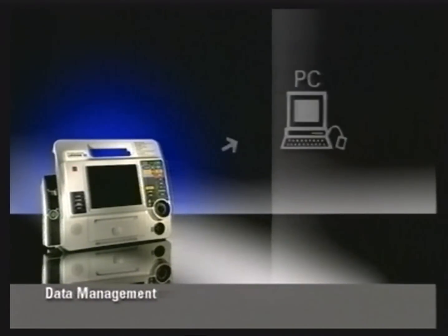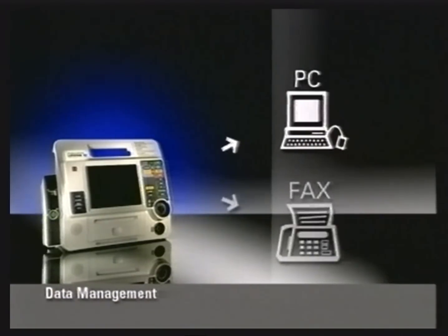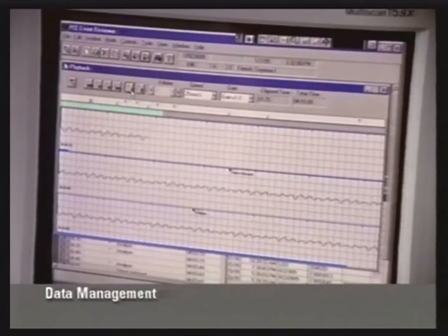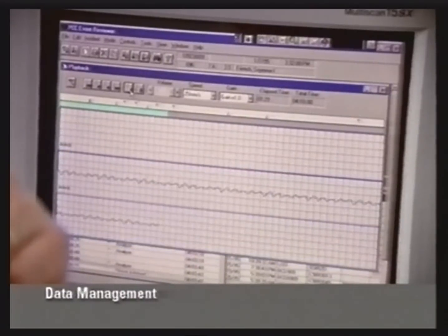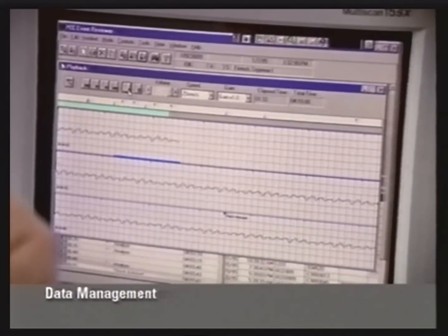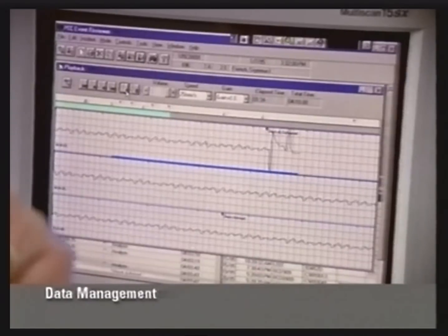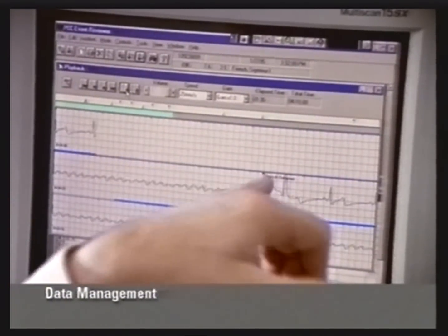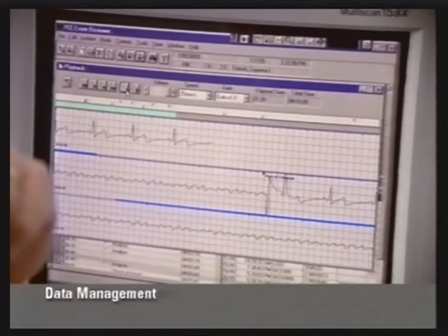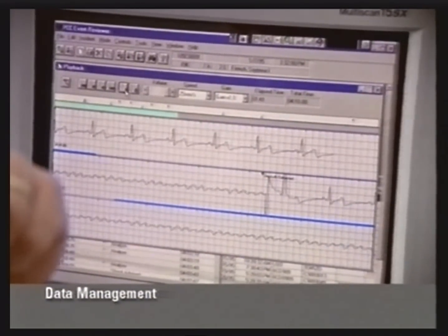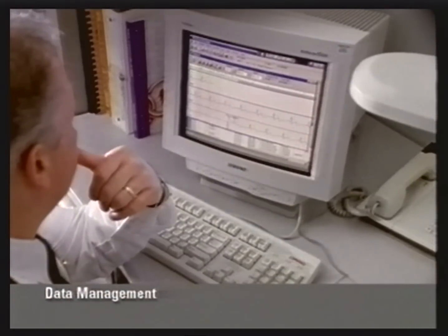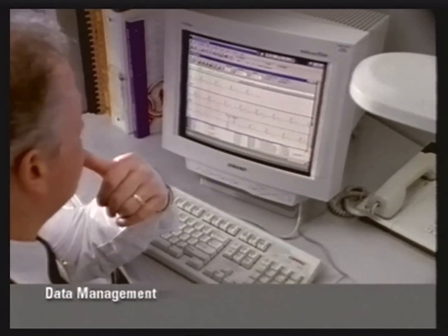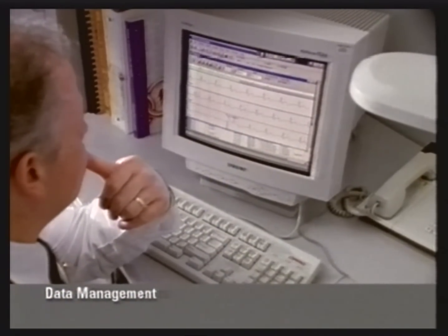Patient data may be transmitted to a PC-compatible computer or to a Group 3 Class 2 or 2.0 fax machine. A continuous ECG report consists of single-lead ECG data. This data can only be viewed by the CodeStat Reviewer program. Approximately 45 minutes of ECG monitoring can be stored by the Lifepak 12 defibrillator monitor. Code summary data, 12-lead ECG reports, and the continuous ECG reports can be transmitted to a PC equipped with the CodeStat Reviewer program for data collection and post-event review.